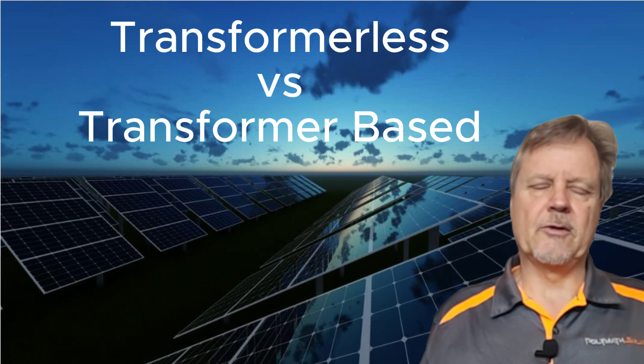A transformer-based inverter can handle much higher inductive loads than a high-frequency one. That sounds complicated, but if your house has typical household appliances, a high-frequency, transformerless inverter can work for you. But if you have high inductive loads - big motors, big transformers, welding equipment, air conditioners, big motors starting and stopping, cold rooms - be very careful using transformerless inverters. They do not have the capacity to handle inductive loads. Keep that in mind.